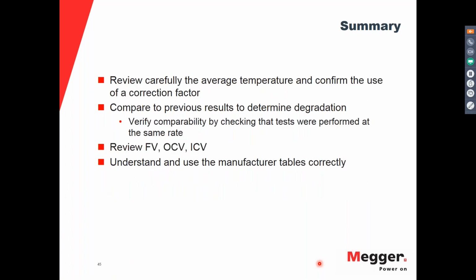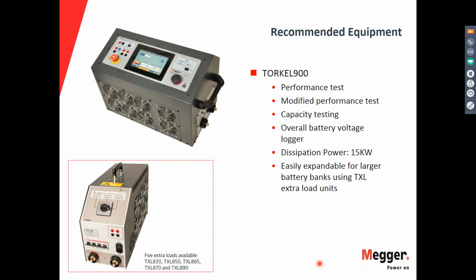When reviewing the results, carefully check the average temperature and confirm the use of a correction factor. And always compare to previous results to determine degradation of the battery and verify that the tests were performed with the same rate so you can actually compare results. If not, comparability is going to be difficult to achieve. Review all of your voltages in the test report and understand and use the manufacturer's tables correctly. So with this, we conclude the actual technical presentation.